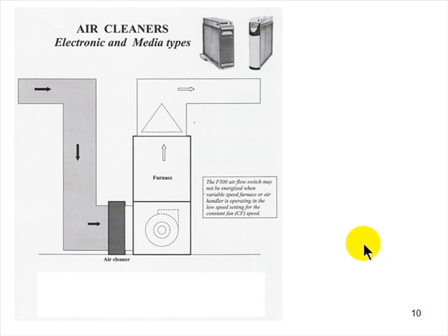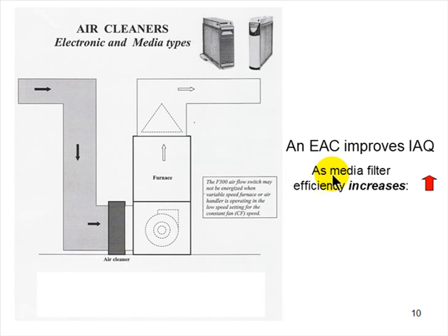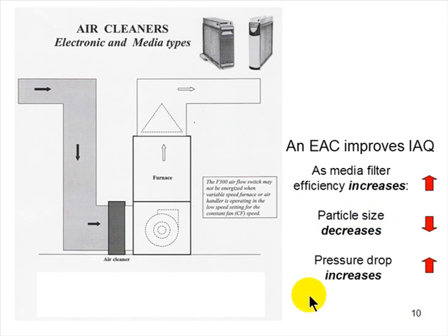Electronic air cleaners in general, let's talk about them. We'll talk about electronic, and we'll talk about media filters. If you have an EAC, electronic air cleaner, you improve the IAQ, the indoor air quality. Any of these filters improves the indoor air quality. Now, if you have a media filter or an electronic air cleaner, as the media filter or the electronic efficiency increases, particle size decreases, pressure drop increases.